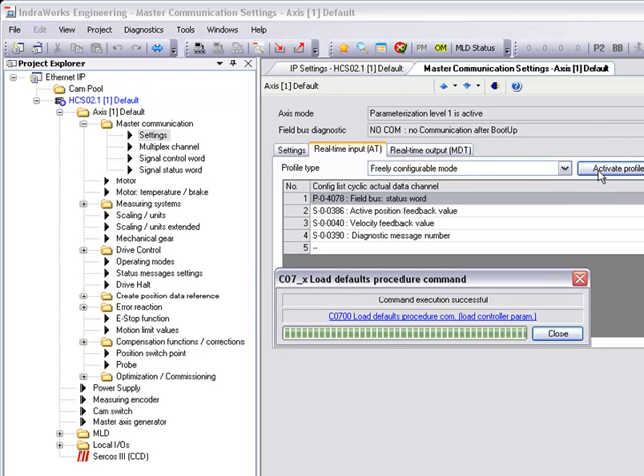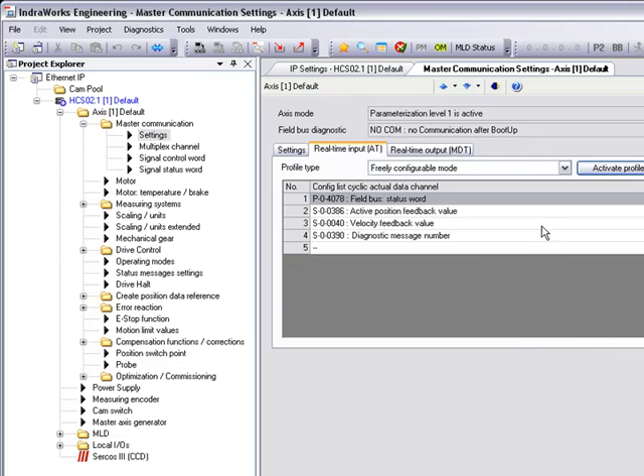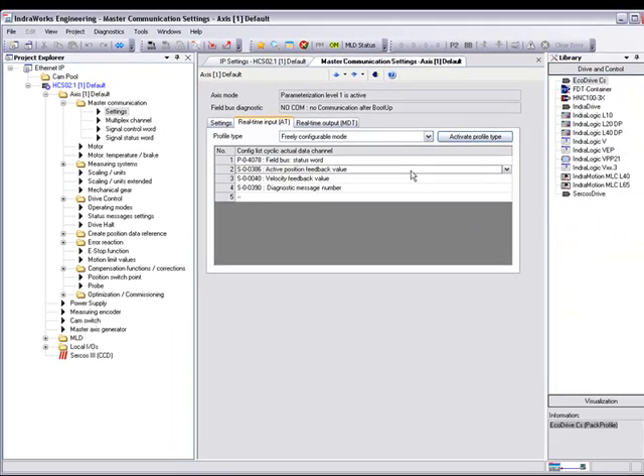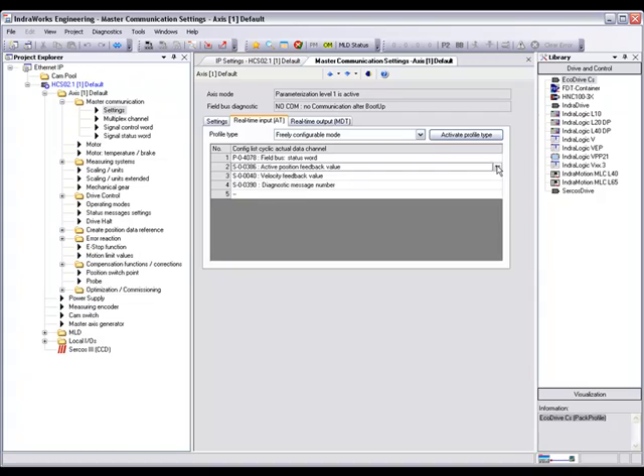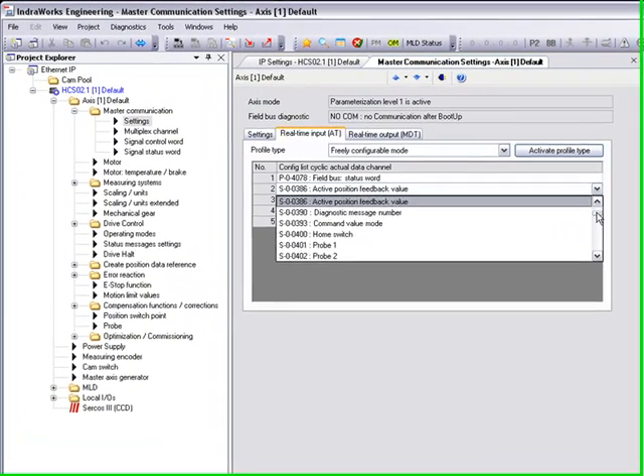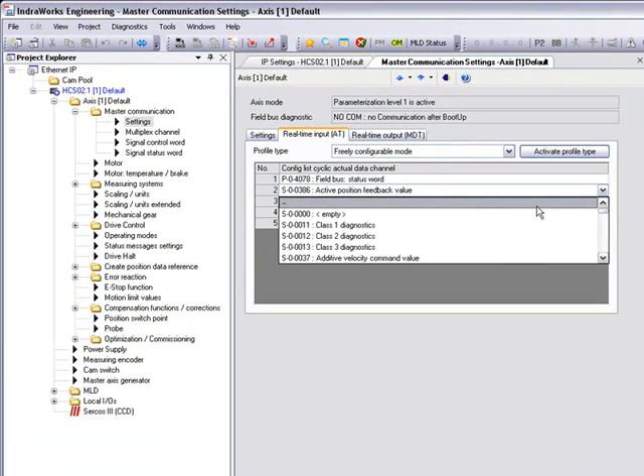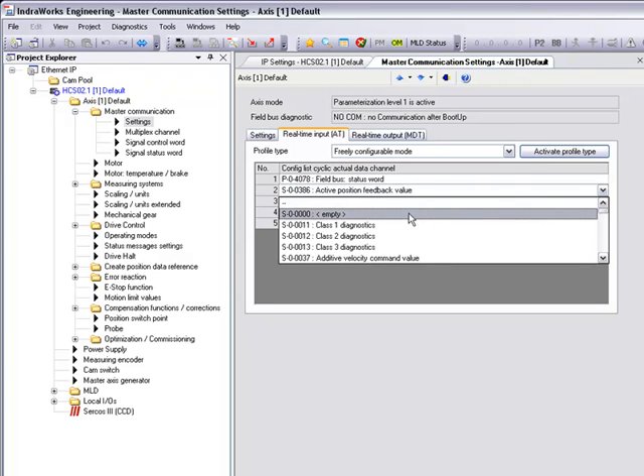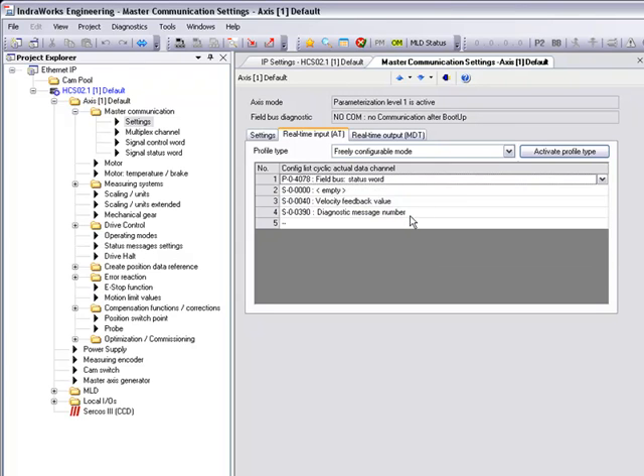Once our profile type has been activated, our field bus status word is automatically added to line 1 of our configuration. Our field bus status word is a 16-bit word and since we'll be communicating using 32-bit words using our PLC, we'll set up an empty spot in line 2.